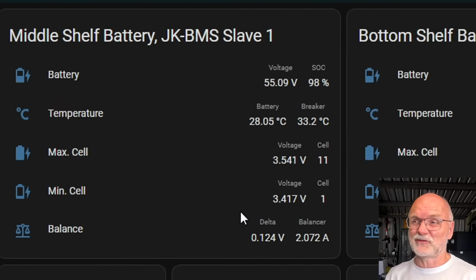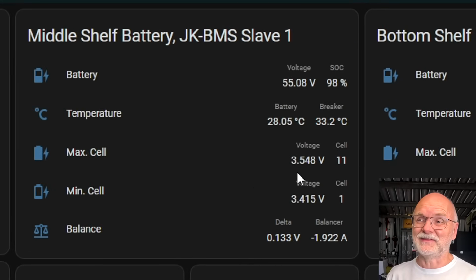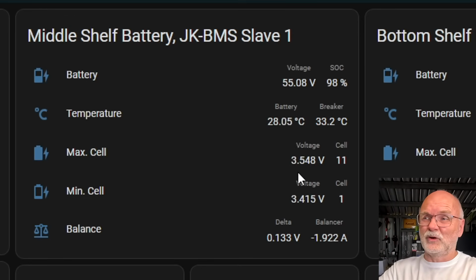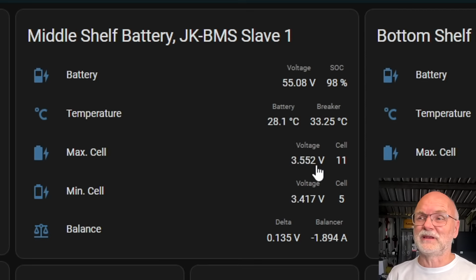Yeah, this one has only a 0.6 amp balancer and is doing a bit of balancing. We are over 10 millivolt deviation. Middle shelf obviously looks completely different. It is balancing cell number 11 because it thinks this is the cell with the highest voltage, but it is only the cell with the highest connection voltage. The problem is the connection and the current going through, more resistant, have a higher voltage.